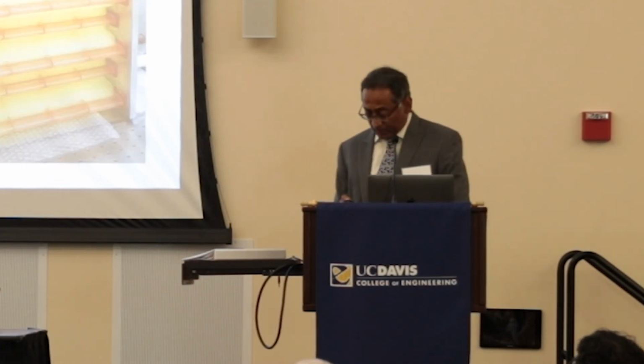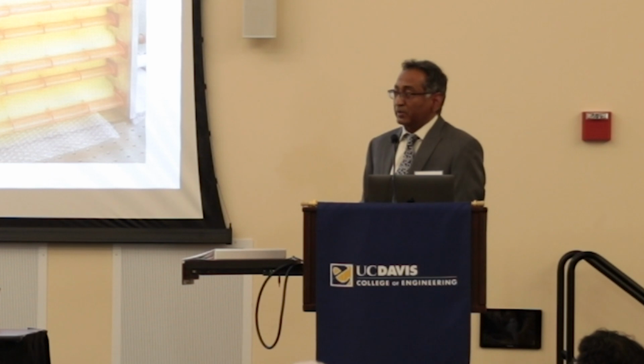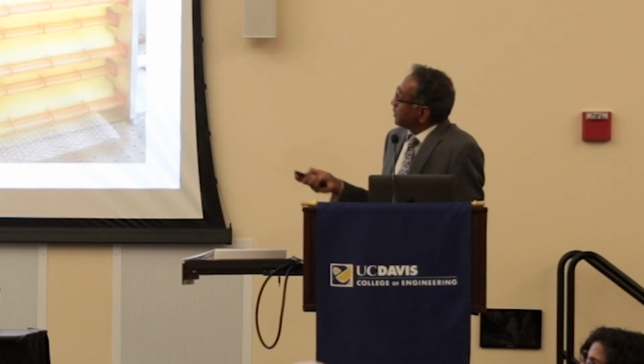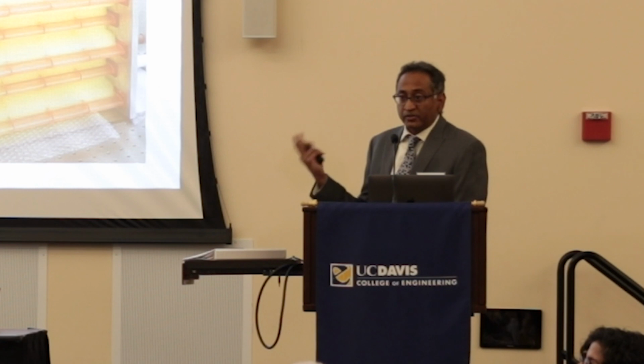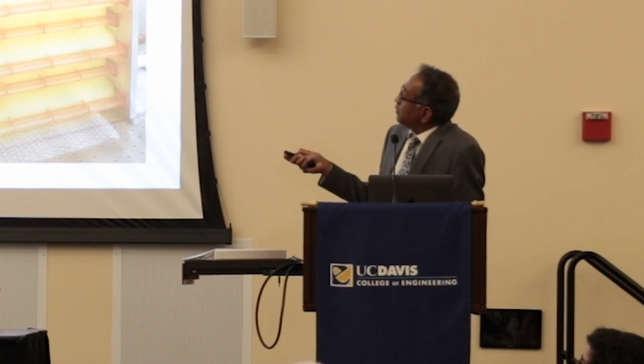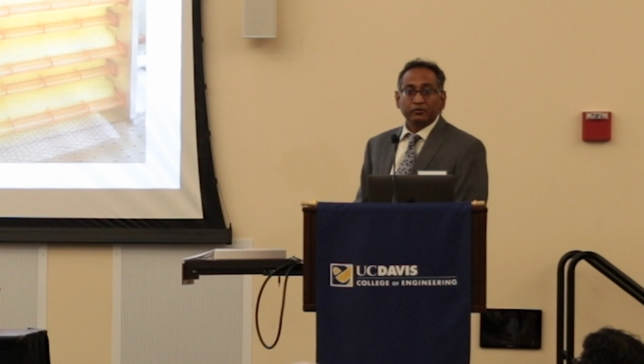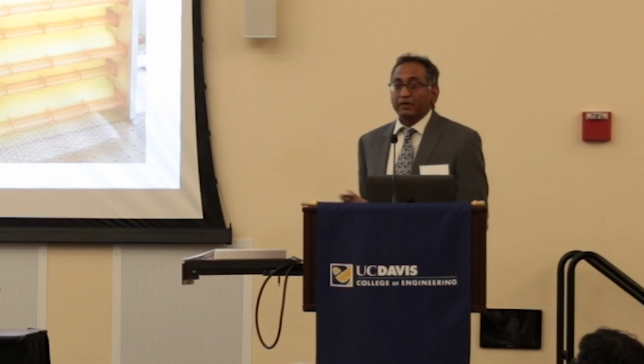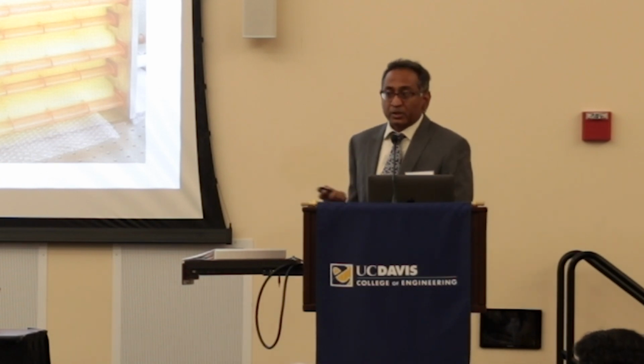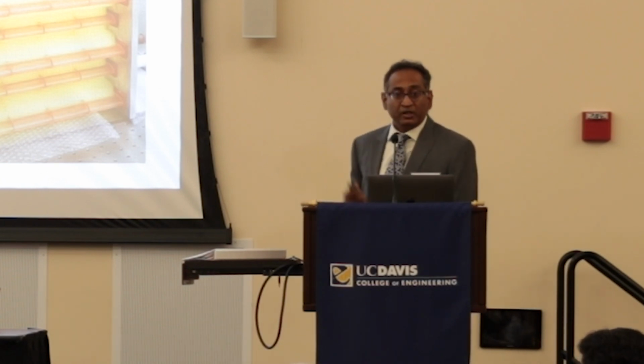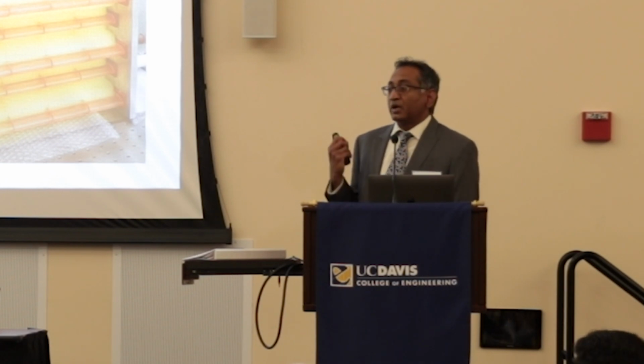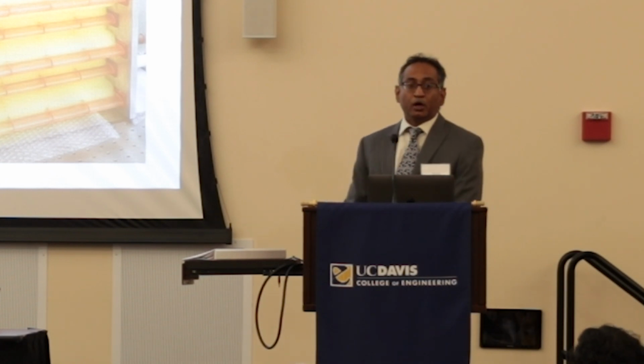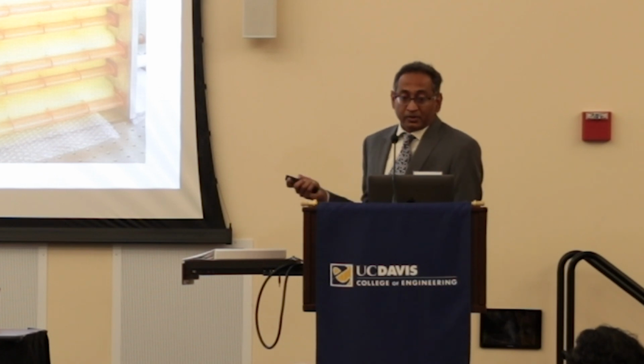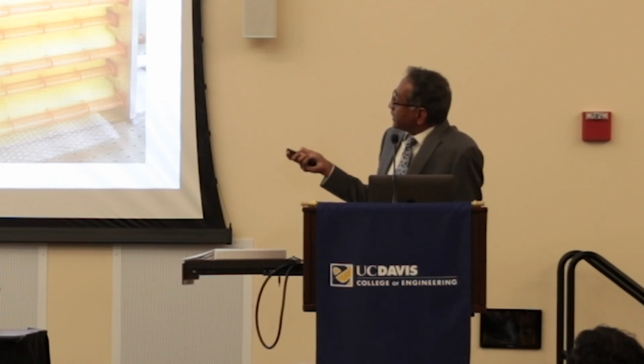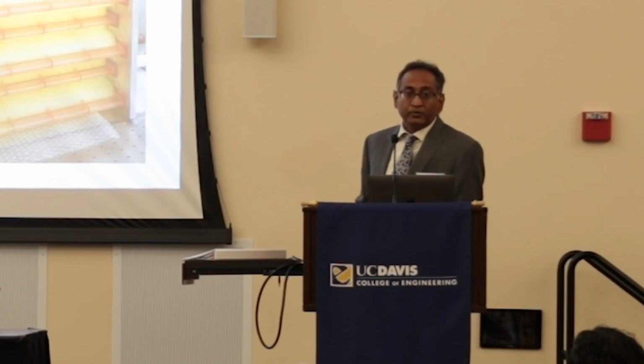Now I talked about global warming potential refrigerants being a problem, and over here on the top left I've shown some GWP numbers for refrigerants that are used in these heat pumps and air conditioners. We have a mandate in California of going to less than 750 GWP by 2030, but eventually we see down the road that we'll have to use natural refrigerants to get away from this GWP problem. Natural refrigerants, we are talking about propane, for example. It's a very good refrigerant for heat pumps, but it is flammable. So almost necessarily you have to use a secondary loop to bring heating or cooling into the house if you use a refrigerant like propane.